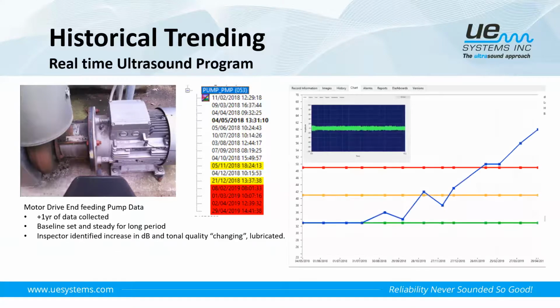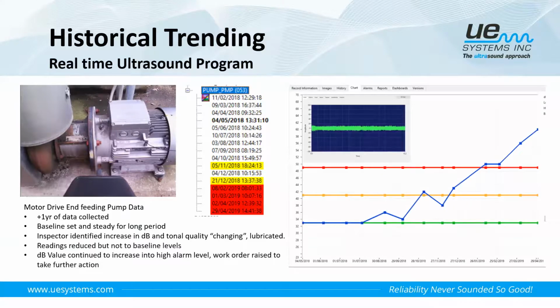So the baseline was set and was steady for a period of time, and we can start to see the decibel level increasing over time. We can see from the baseline and from the time and out time waveform we see on the screen there, smooth and uniform to begin with, and then it started to increase.